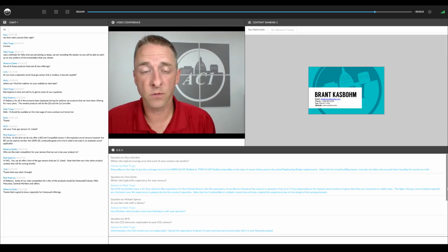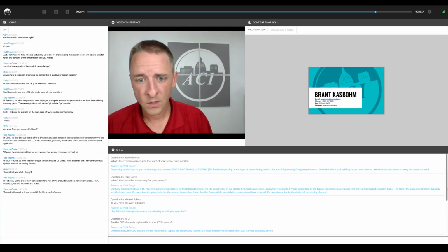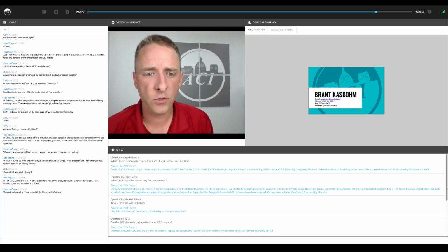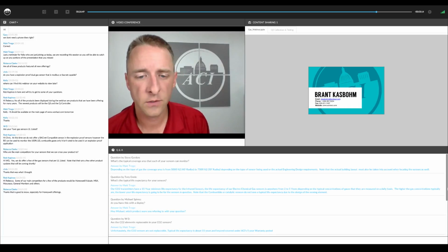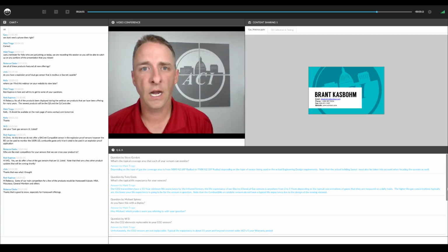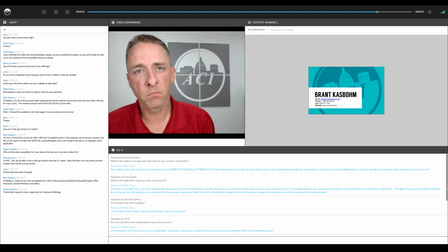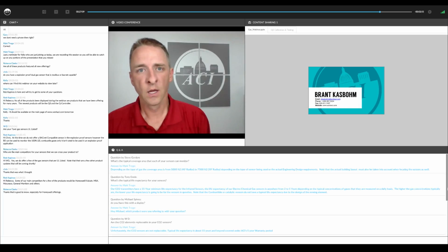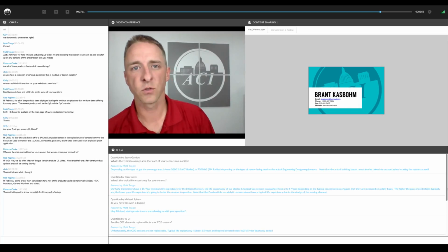I don't know if there is one available for you. Question about VOC sensors. Do you have a VOC sensor or transmitter? At this time, no, we don't. We're monitoring it. We're keeping our eyes on the marketplace for VOC sensors. As of now, the reason we don't have a VOC sensor is because there's no set industry standard, whether that's via ASHRAE or via national building codes, as to what levels of VOCs are considered hazardous, or when there is a need for additional ventilation.